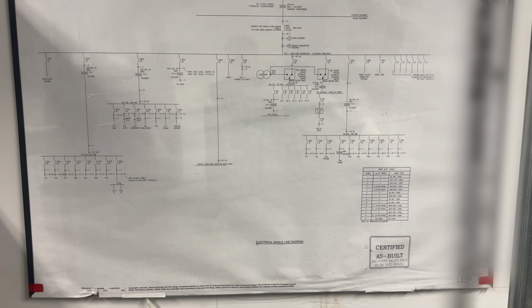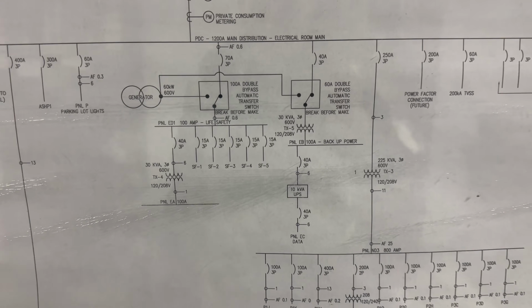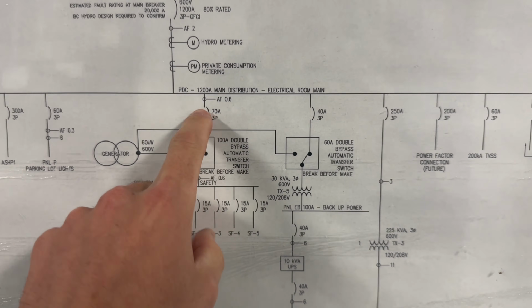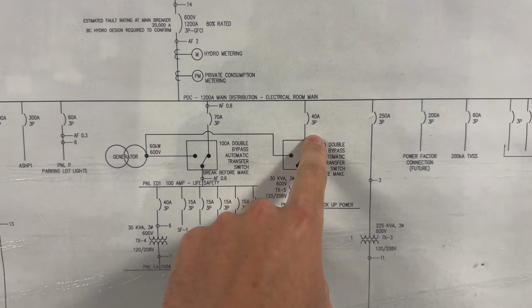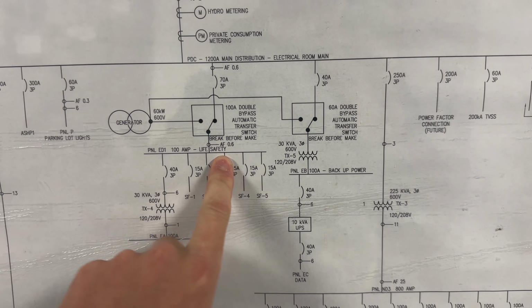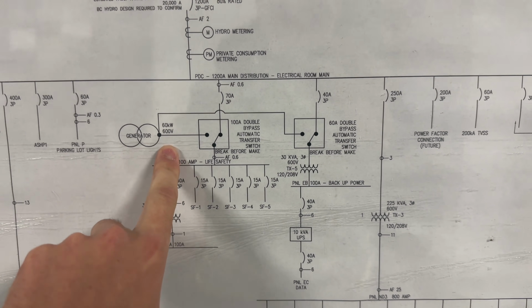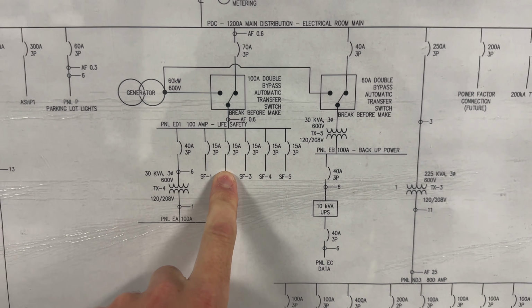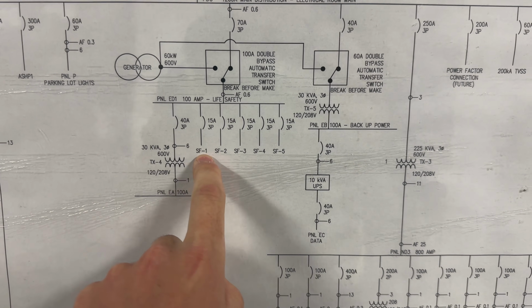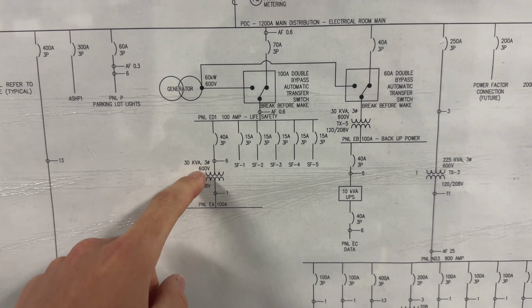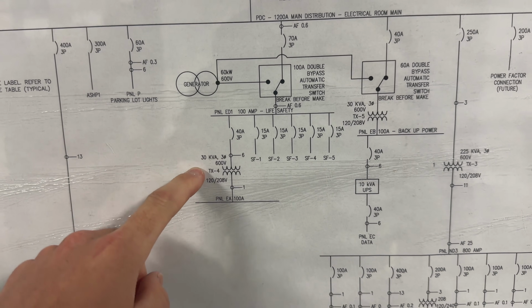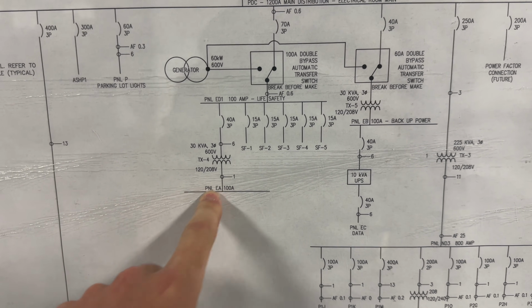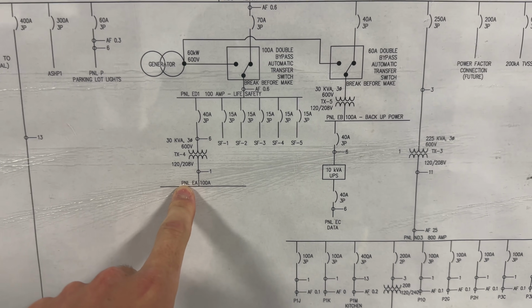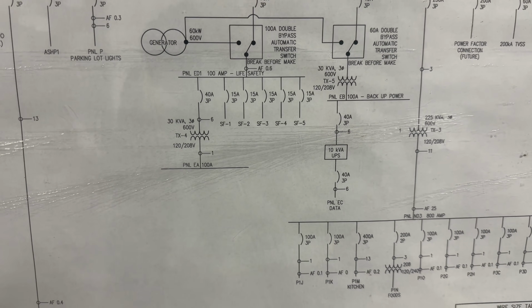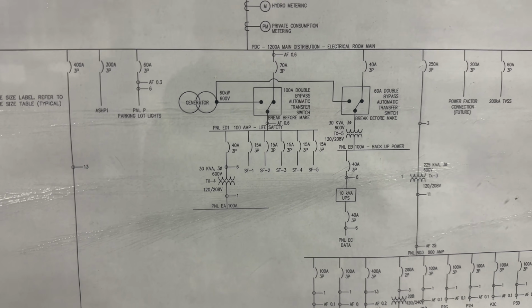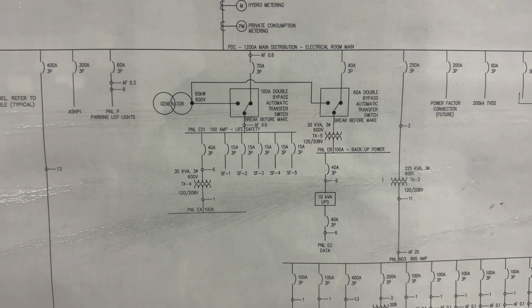On this one line diagram here, you can see exactly where that 70 comes off the 1200 amp main distribution, the 70 and the 40, double bypass automatic transfer switch. That is our generator, 60 kW at 600 volt, and you can see what that's feeding. So this is our life safety. It's supplying all those fire exhaust fans, and then we are also 600 volt on that side going into a transformer. It's taking us down to 120/208, and that is our emergency power at 120/208, which is doing all of the emergency lighting and pretty much everything other than those supply fans.